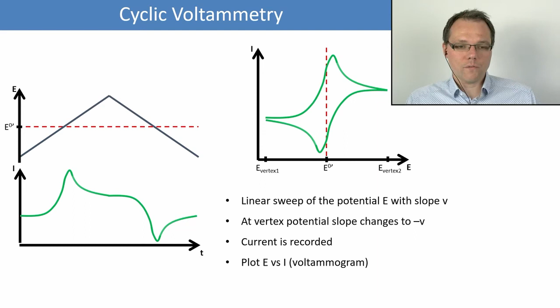So in our app PS Touch, you can set which technique you want, and as I said, we're going to use cyclic voltammetry. We're going to set our current ranges, which are 1 microampere to 1 milliampere, and the current range is basically defining how sensitive the potentiostat is. So at a low current range, you can measure low currents very well resolved. However, if you have the larger currents, the potentiostat can't handle that anymore.